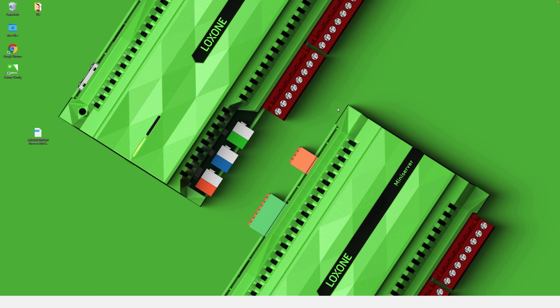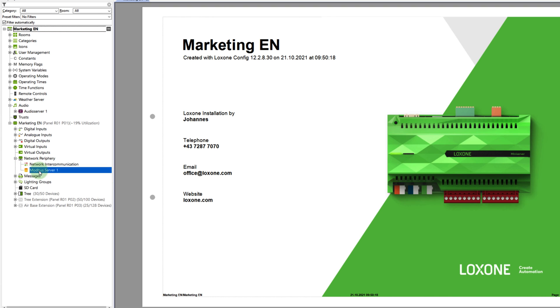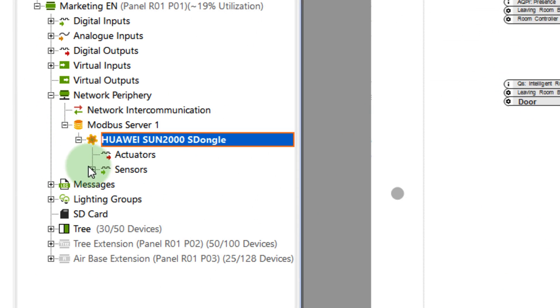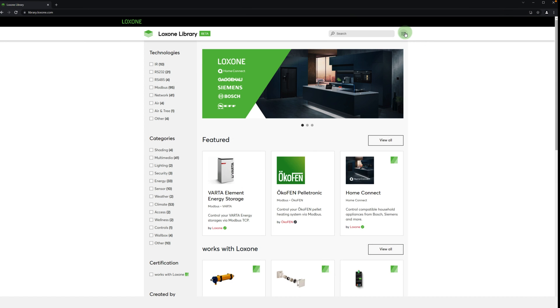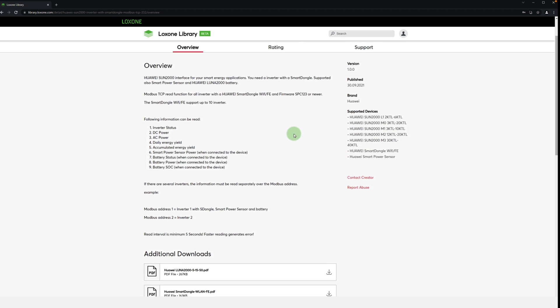Let's have a look at the new Loxone Library in detail. By double-clicking on the downloaded file, the template is added. In my case, the inverter communicates via Modbus TCP, so via the network. That means I have to create a new Modbus server network device and can now open the template under the Device Templates option. With just those few clicks, all stored inputs and outputs are available. Back in the library, you can log in with your Loxone account — this allows you to rate and leave comments on the template. You also have the ability to contact the creator directly.